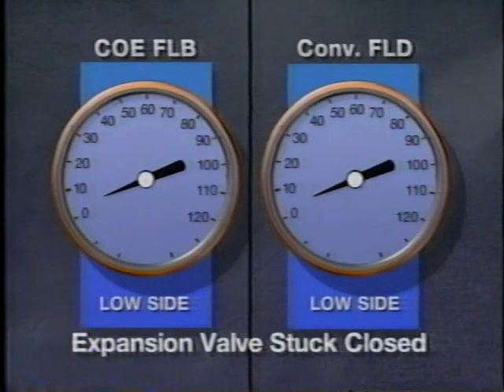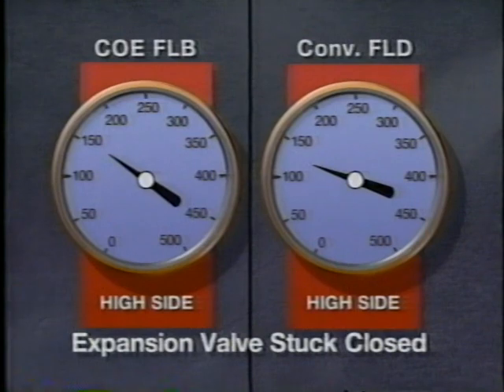If the expansion valve is restricting the flow of refrigerant, is stuck closed, or contains a malfunctioning temperature sensor, the pressure on both the discharge and suction sides of the system will be low, although normal pressures can be restored when a hot wet rag is applied to the expansion valve. In this case, the expansion valve must be replaced. Also, if there are any contaminants present in the thermostatic expansion valve, the system must be purged or flushed.